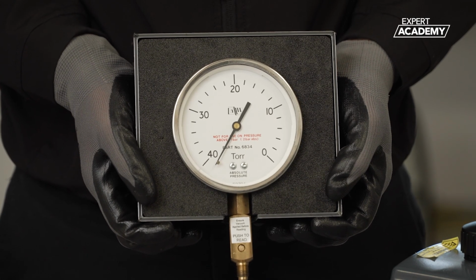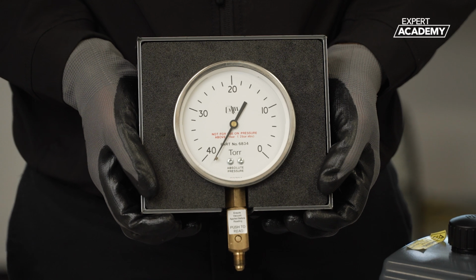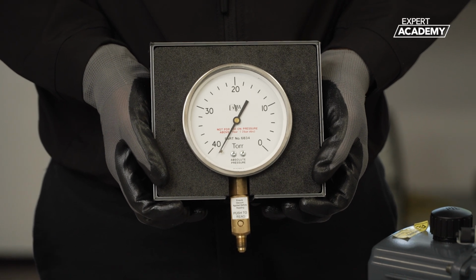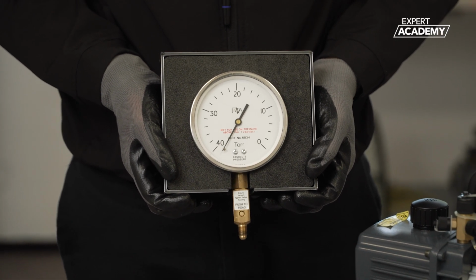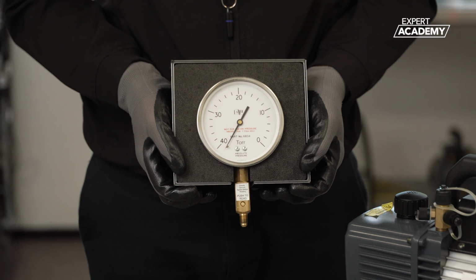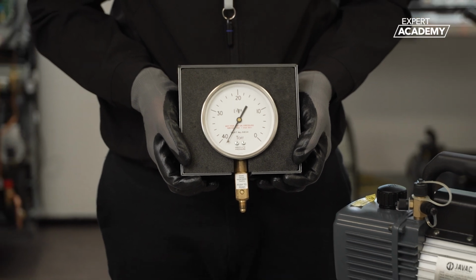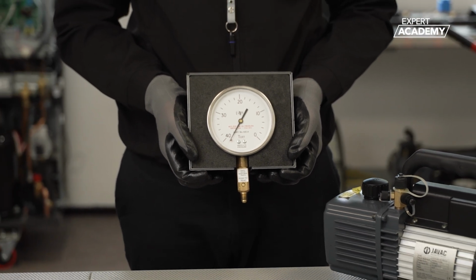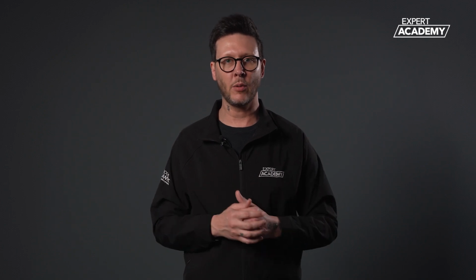Used alongside a vacuum pump, a torr gauge measures even the smallest absolute pressures and provides readings on the dehumidification status of a system, i.e., have we drawn out all microns of moisture, oils or foreign gases. They are available in digital and analog equivalents.